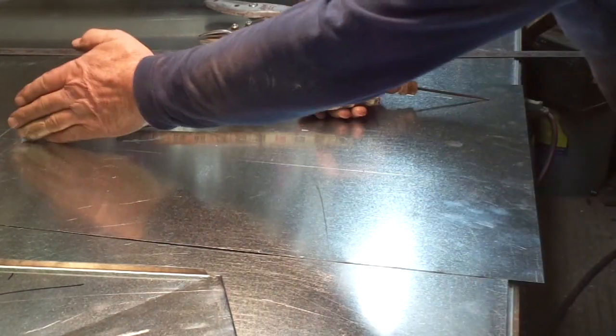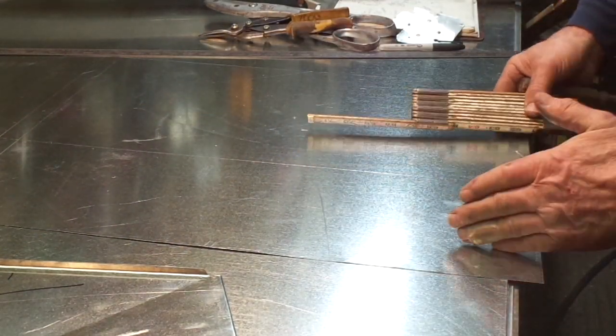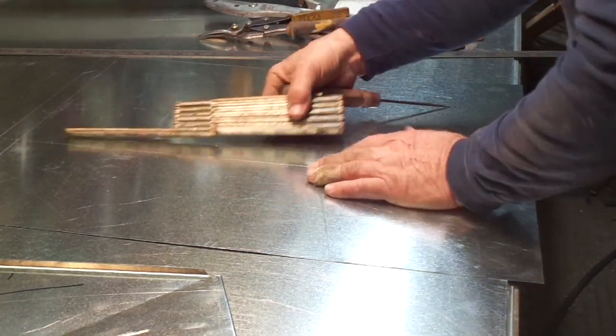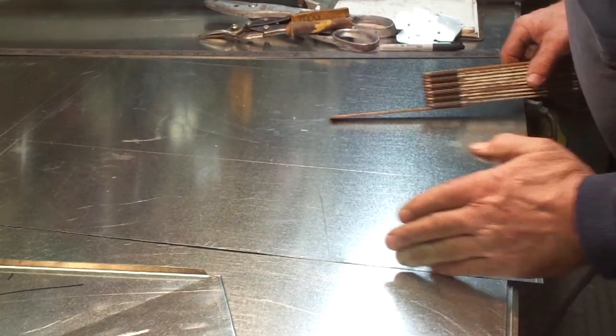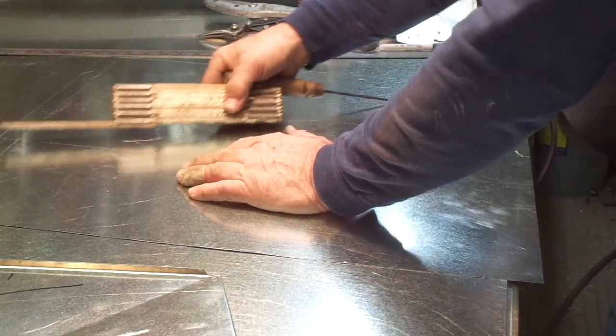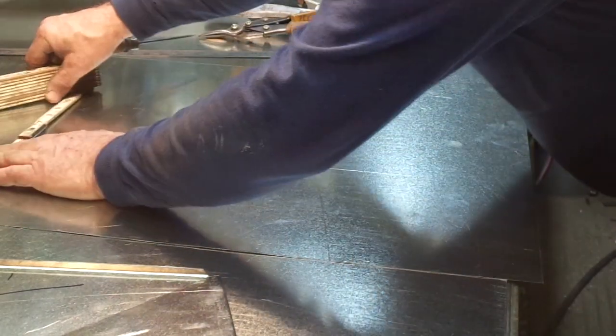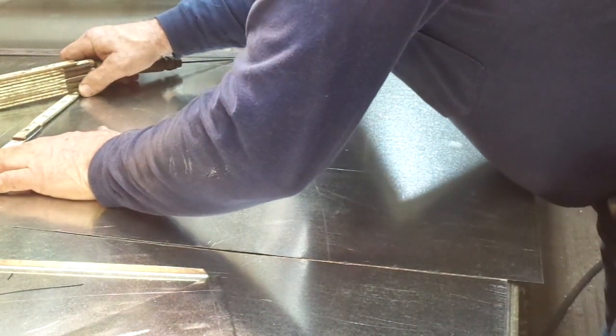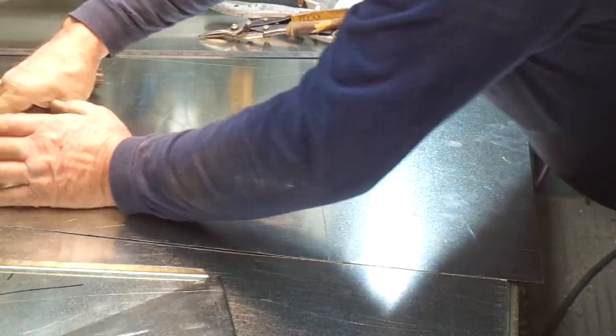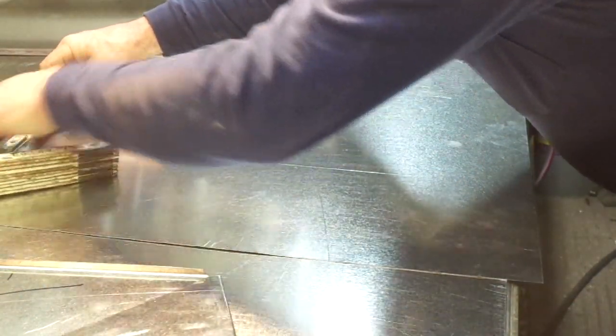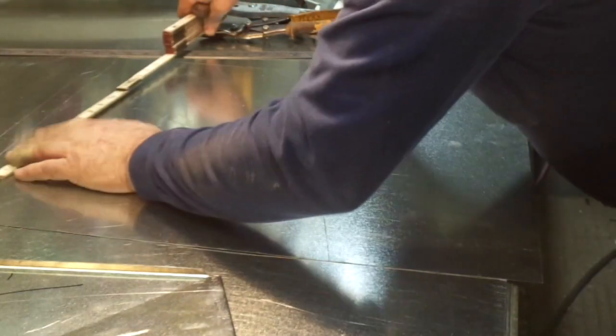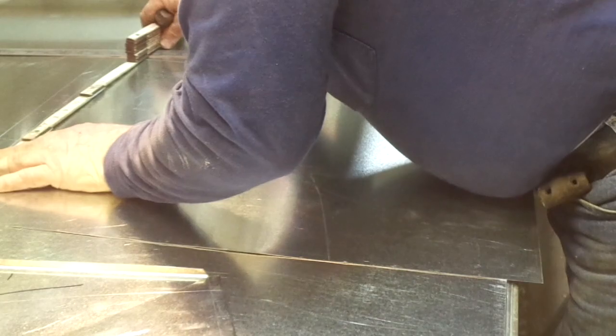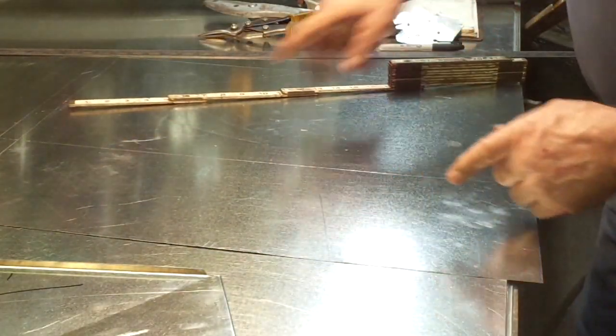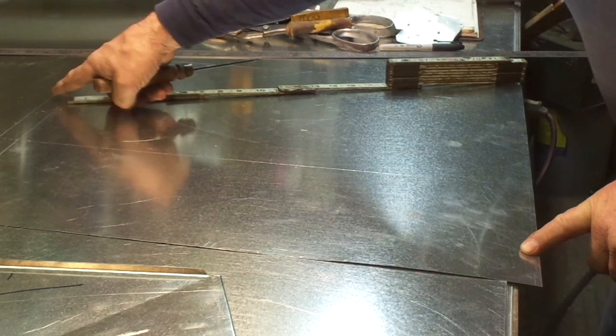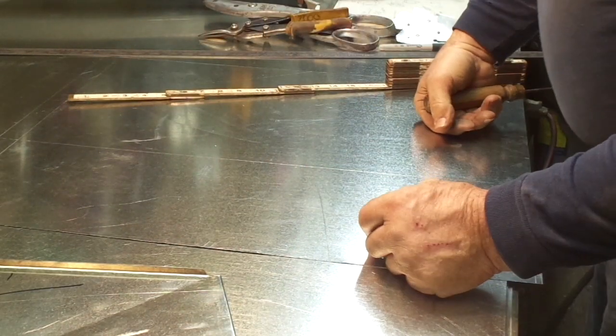So up here on that center line right here, to make sure that you have an equal taper, that's why you have to have that center line. So on that center line up here, you take half of the dimension you want to transform to. That's 10 3/4 inches. Half of 10 3/4 is 5 3/8. So you come right here and put a mark at 5 3/8 over here. Come off of the center line, 5 3/8 over here. Double check that, make sure it's 10 3/4. Make sure you did the math correctly in your head. 10 1/2 inches. Now we connect the dots from there to here, there to here. And we have an equal taper transition.